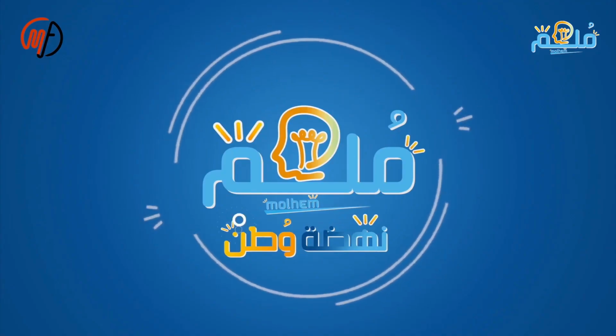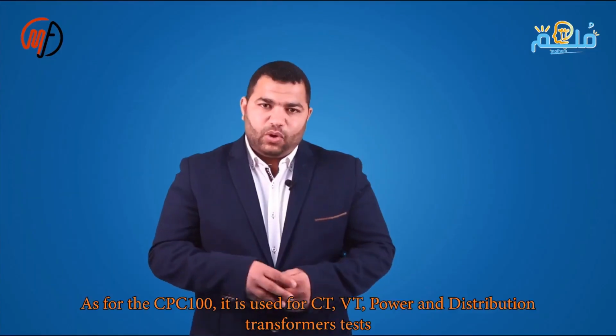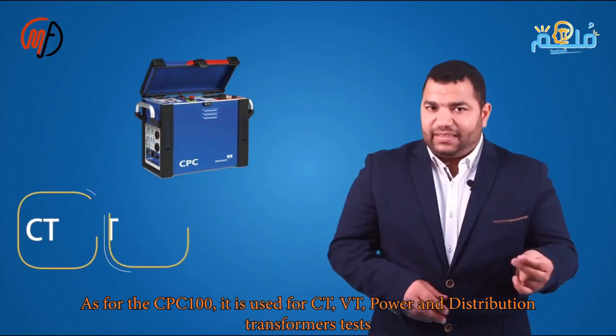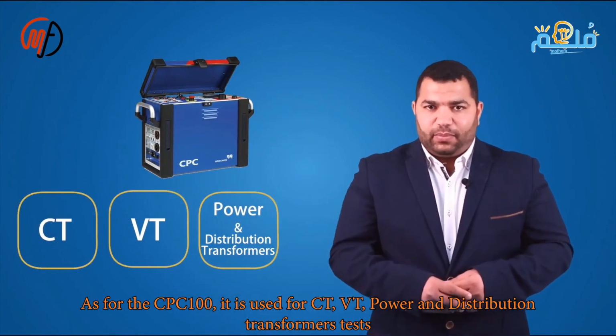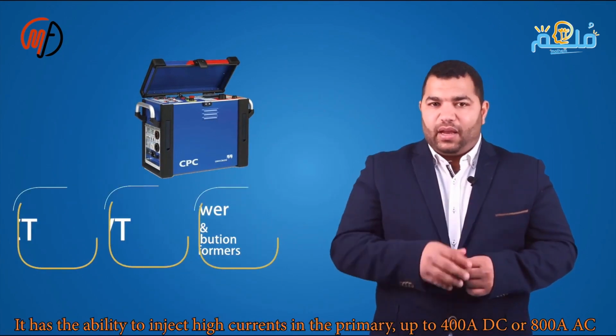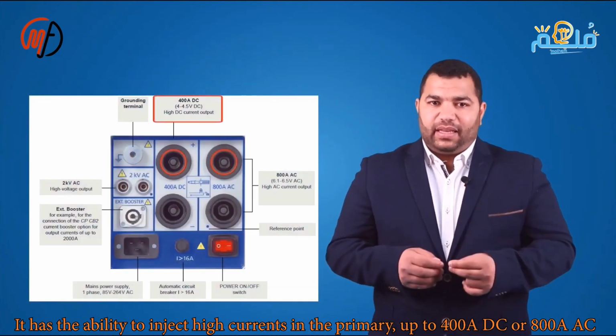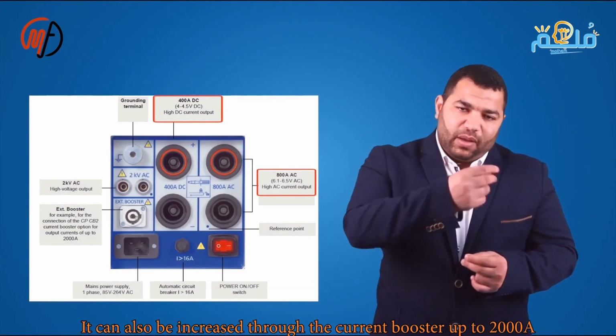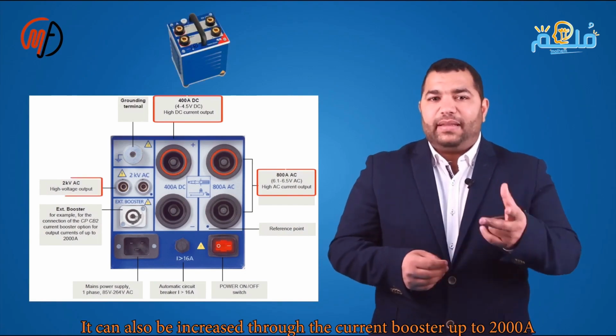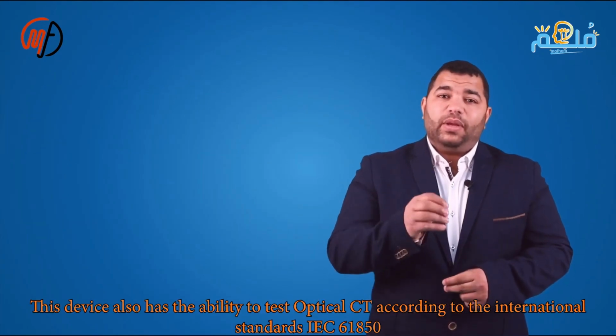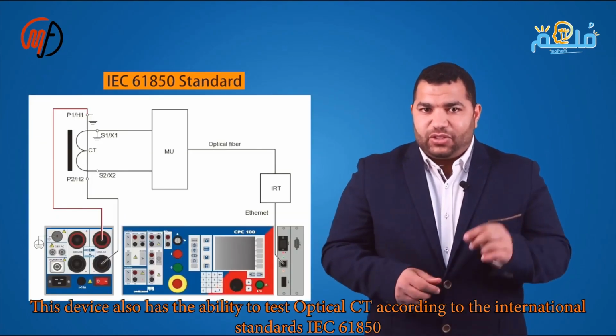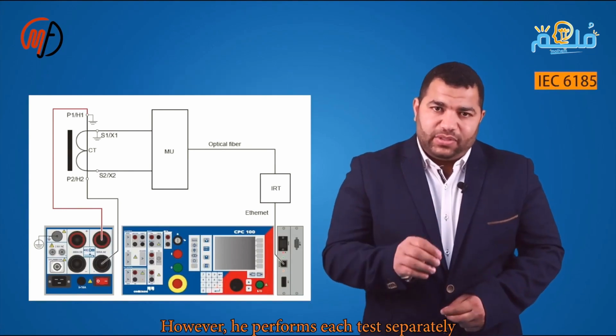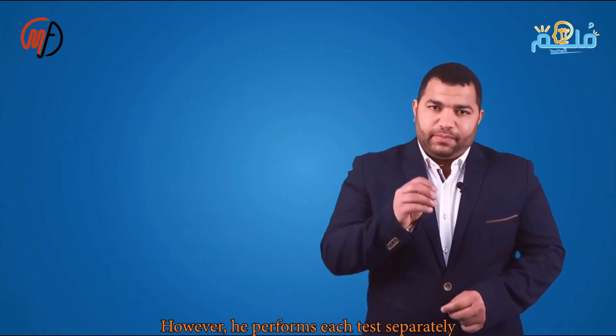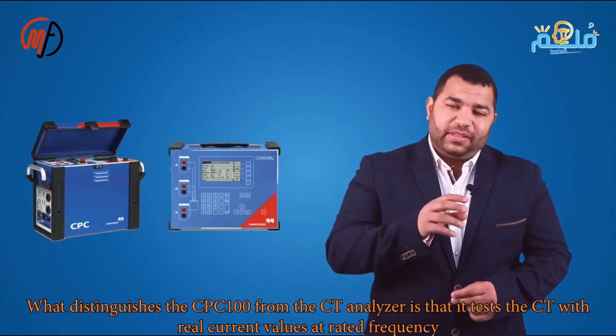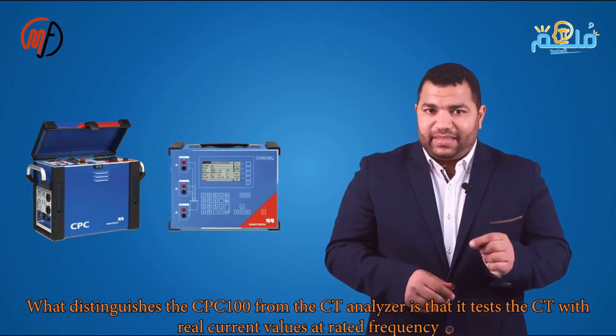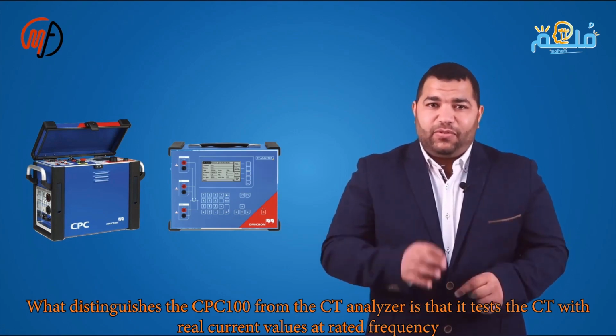The CPC100 device is used for testing CT, VT, power, and distribution transformers, and it has the capability to inject high currents in the primary up to 400 amps DC or 800 amps AC, and it can also be increased through the current booster up to 2000 amps. It also has the ability to test optical CT according to international standard IEC 61850, but it performs each test with a separate connection. What sets the CPC100 apart from the CT analyzer is that it tests the CT with real current values at rated frequency.